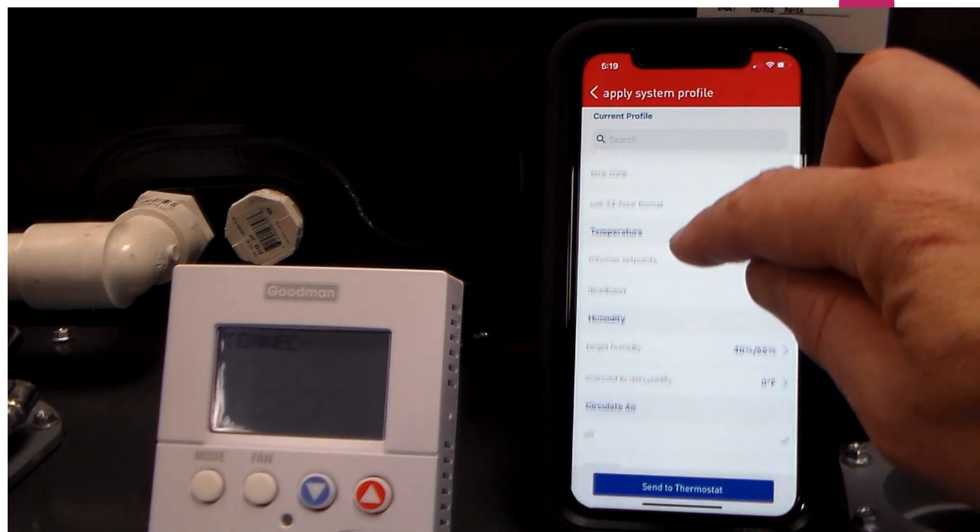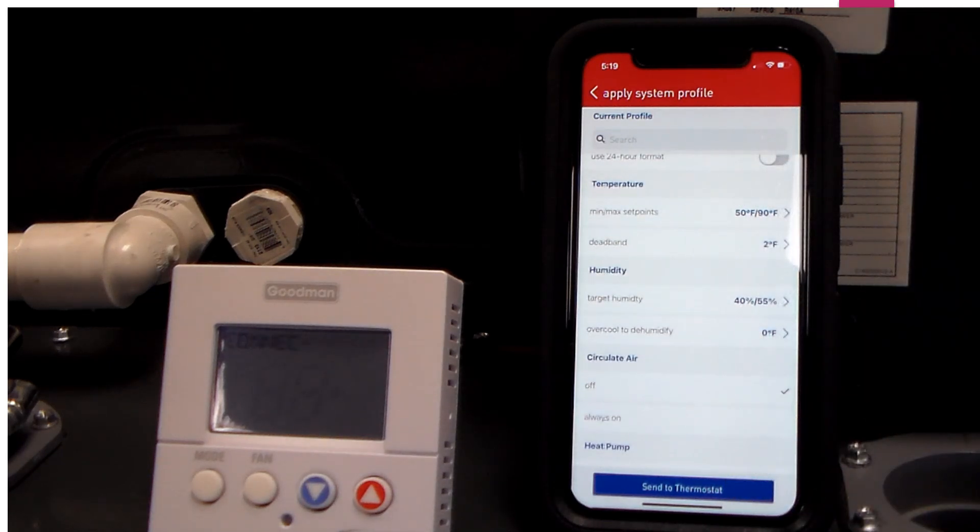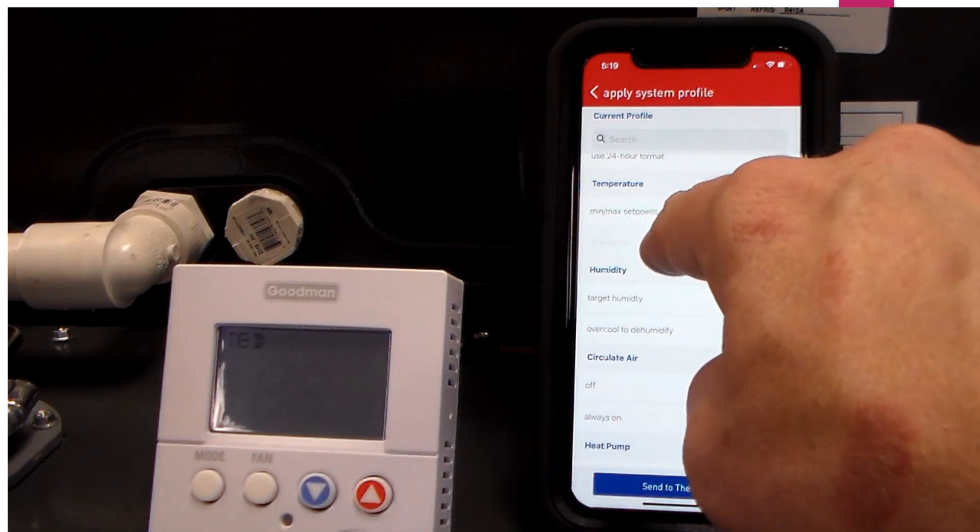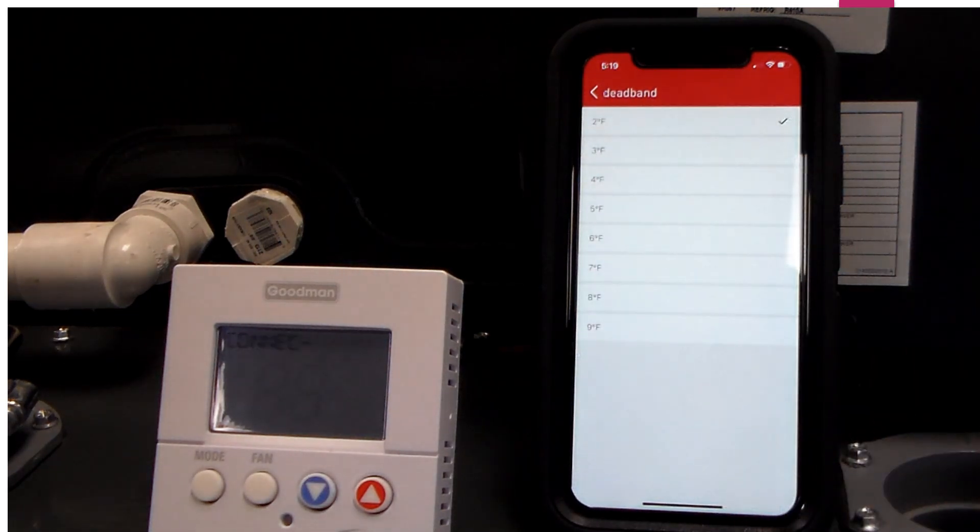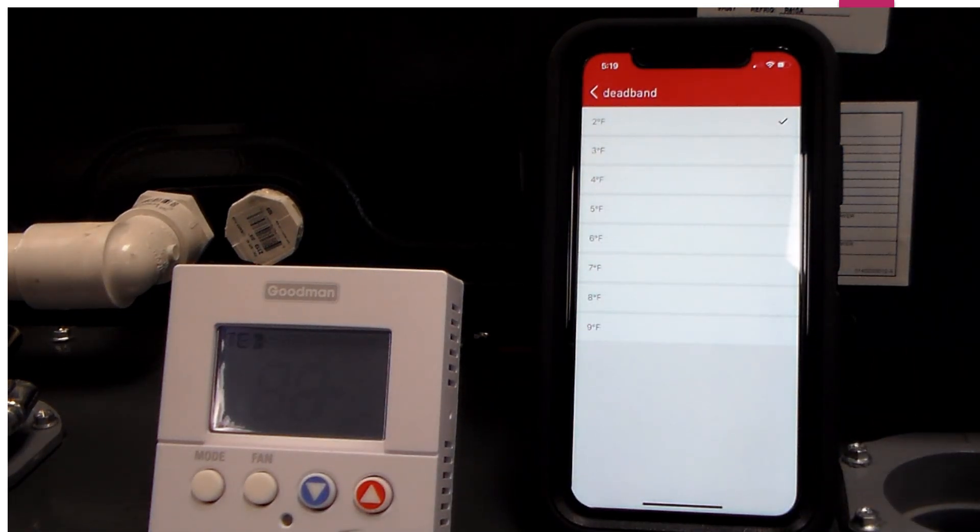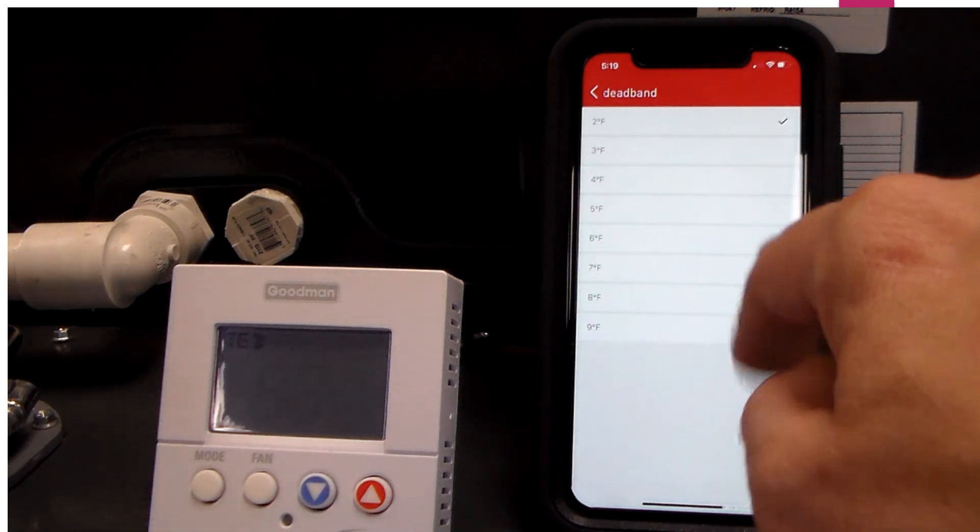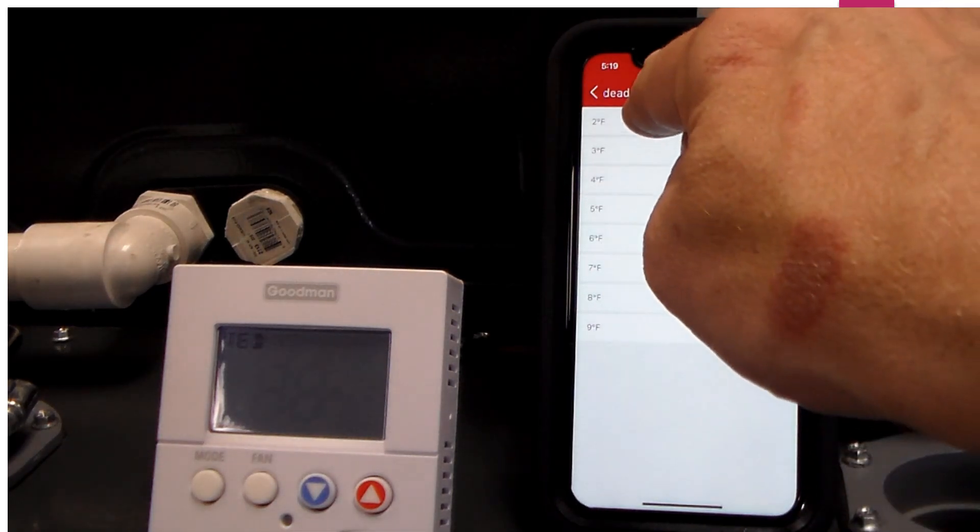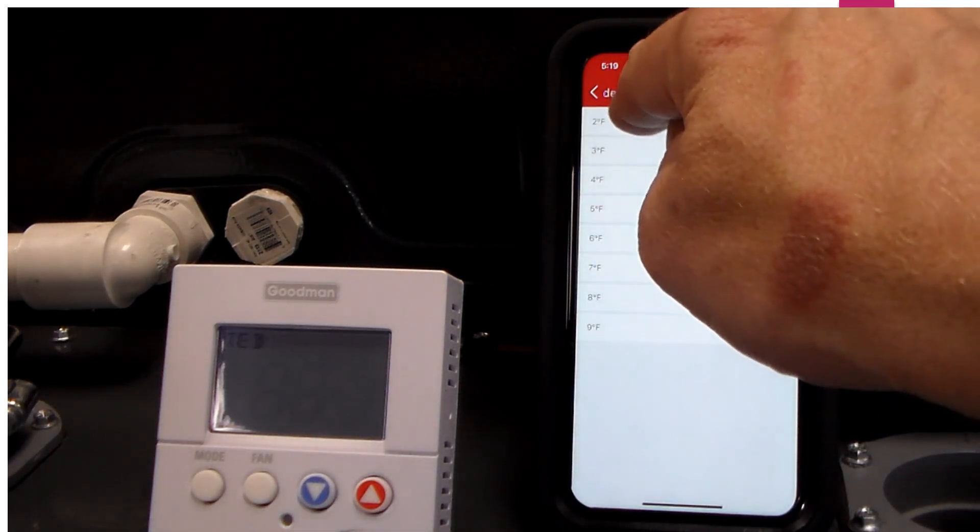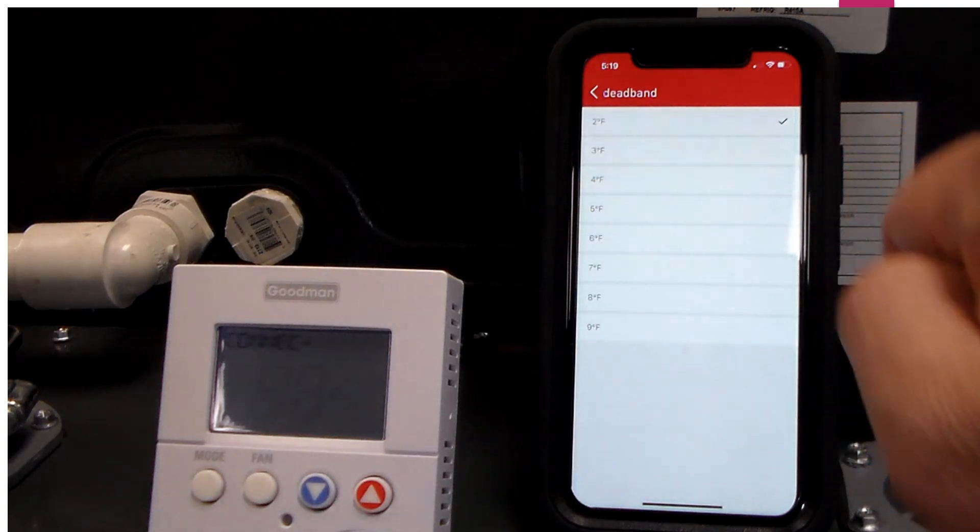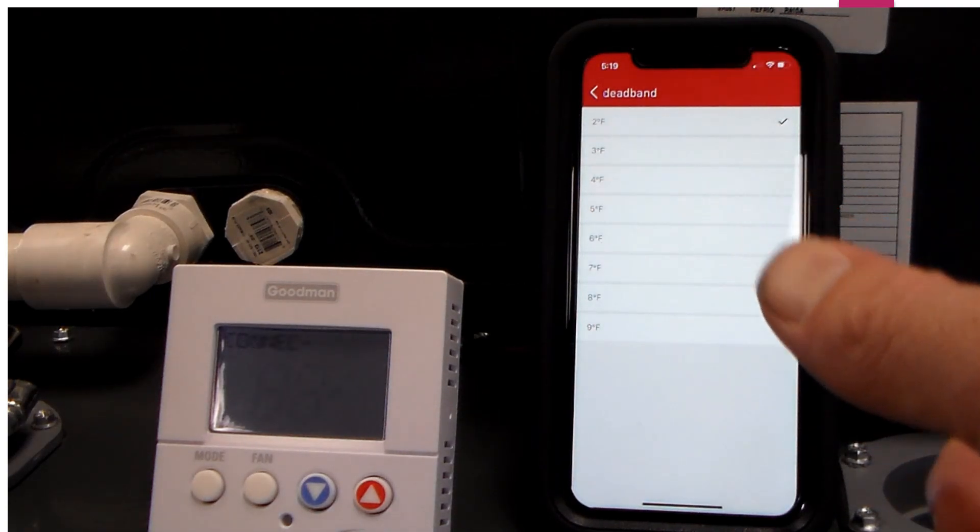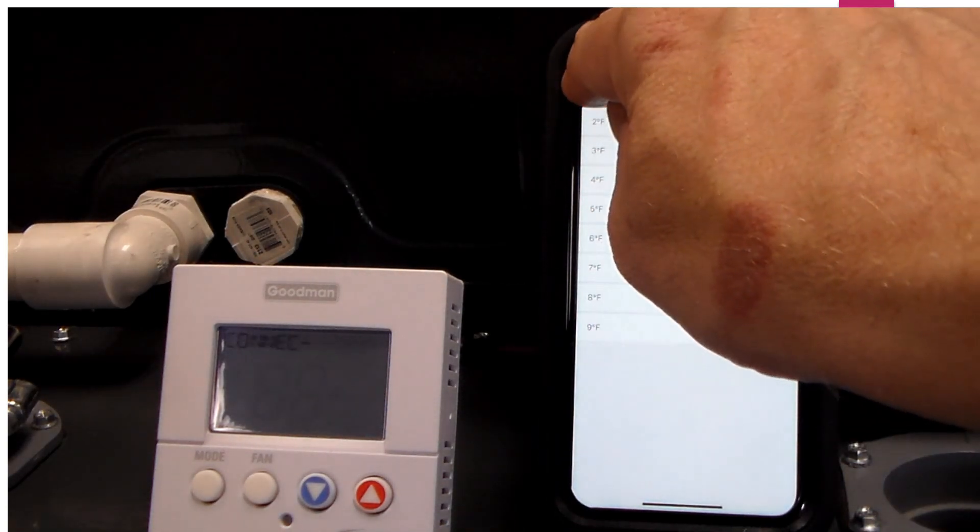When we get down to temperature, there's a couple things I want you to make note of. Notice this dead band setting here. A lot of these thermostats are shipping from the factory with a four degree dead band. You want to make sure that you correct that to a two degree dead band to give you a little tighter control of the system.